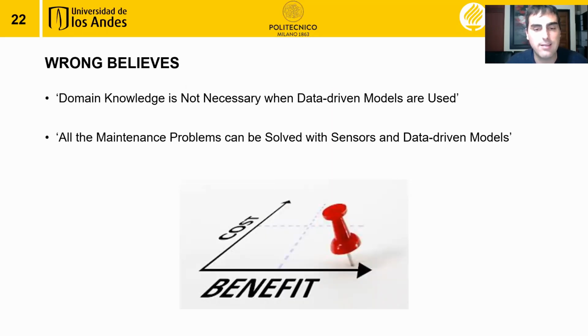What we saw is that this case study can also help to cancel wrong beliefs in students. Sometimes, with the advent of Industry 4.0 and all these data-driven methodologies, people may think that domain knowledge is not necessary when data-driven models are used. But we can see that we reach 100% accuracy because we start from domain knowledge, since we know that imbalance can be seen, for example, at the frequency of the motor in the frequency domain.